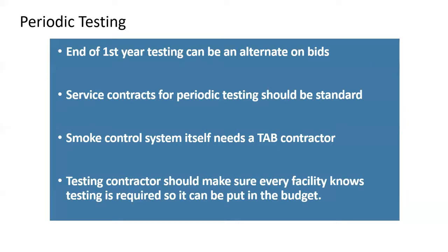And the smoke control system does need a test and balance contractor. The dampers themselves in a few locations need a certified contractor, but anyone actually can do the testing in most cases. But oftentimes that means that the fox is guarding the chicken house. So you really want a contractor qualified that's in there. And then all the testing contractors should make sure that the facility knows they're supposed to do this. Very often they don't even know it, and then they get a surprise. And if you've got a chief who's been in the building for 10 years and has never mentioned it to the owner, and then suddenly he gets nailed, it makes him look bad. He should ask for it in his budget every year.